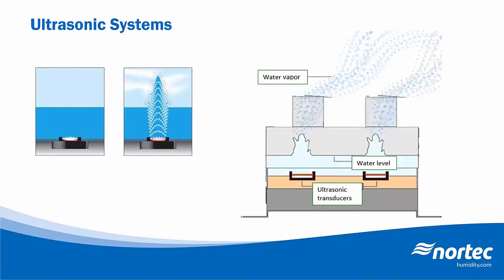The last technology that we'll cover here is ultrasonic systems. So this type of system uses a series of piezoelectric transducers that oscillate at an ultrasonic frequency, which causes cavitation in the water, which effectively releases an ultrafine mist into the airstream. So as with atomizing nozzle systems, ultrasonic units do also require treated water in order to prevent dusting as well as to prevent transducers from scaling up.